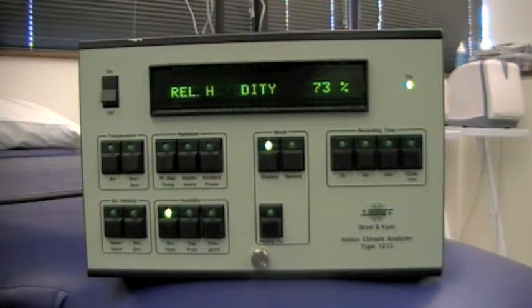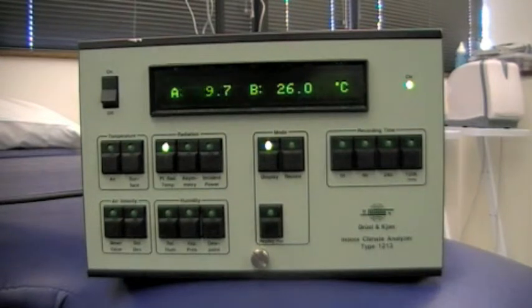Relative humidity has increased, this is because we're actually cooling the air in the room and that's a natural consequence of that. This is the radiant temperature again and now you can see that we've got the blinds closed. We've gone back to a similar temperature difference between the A and B surfaces that we had at the beginning. 29.7 for the A and 26 for the B.